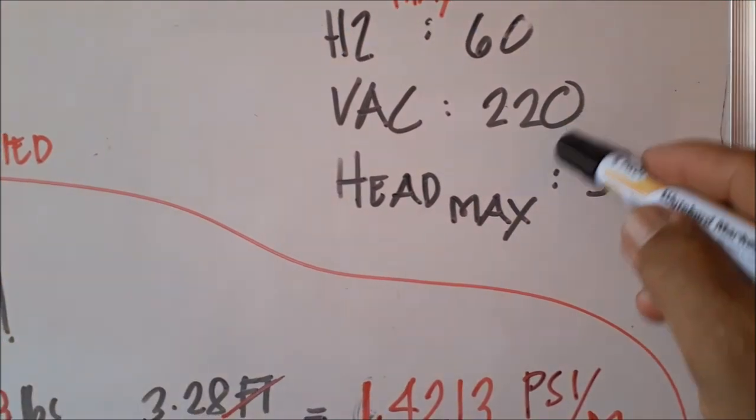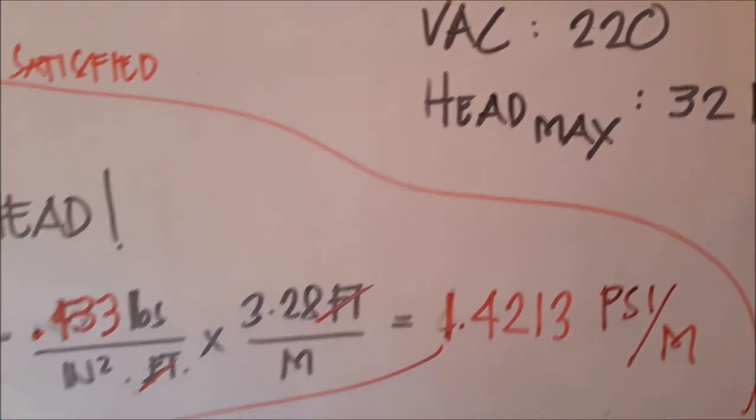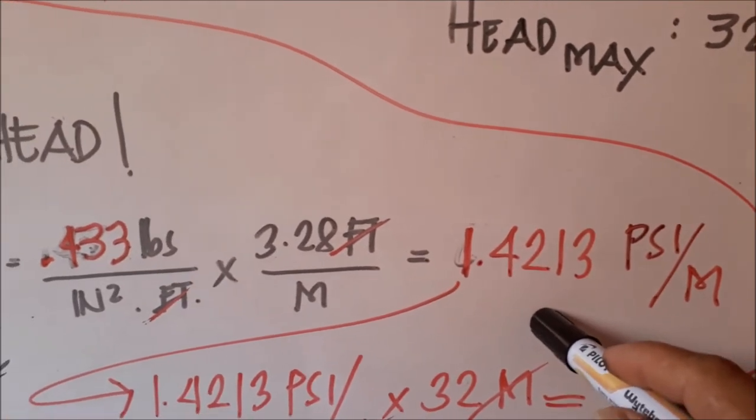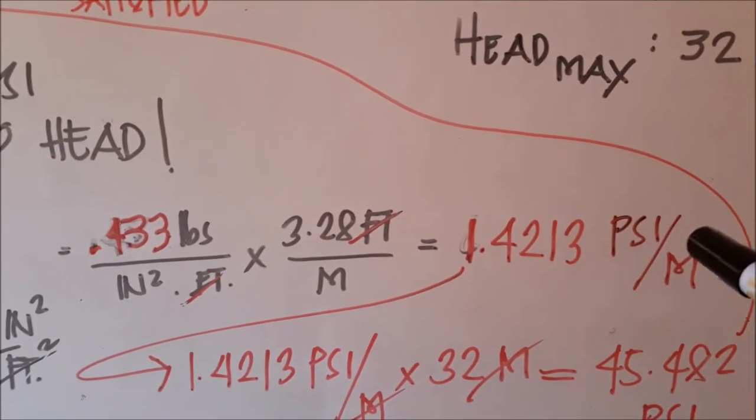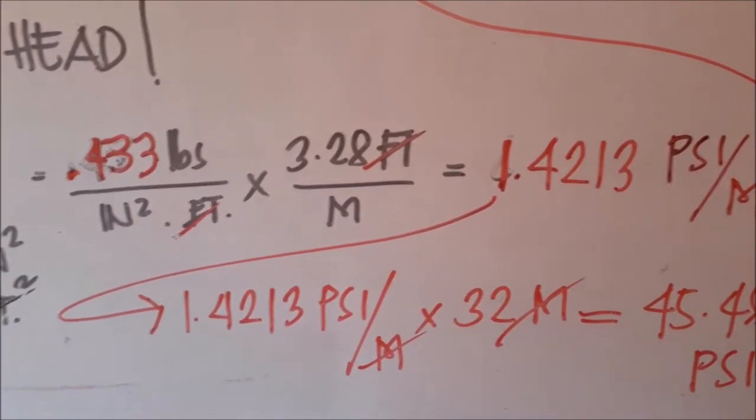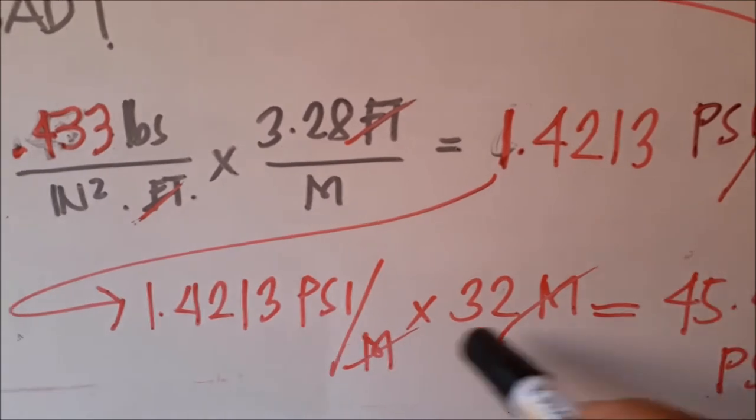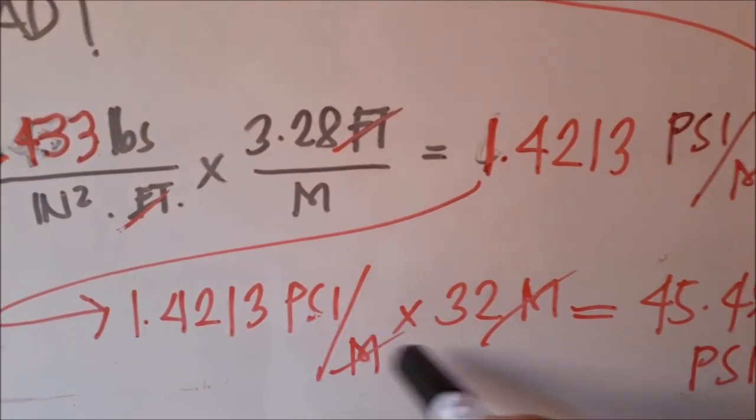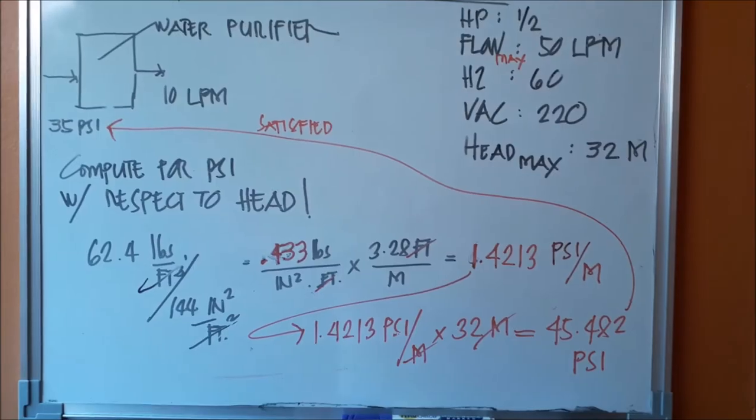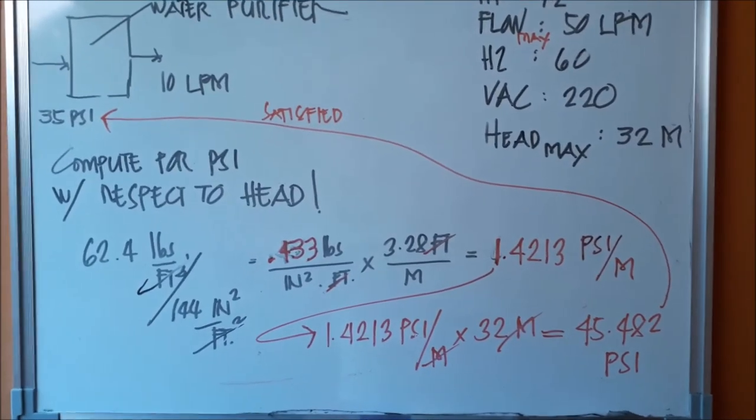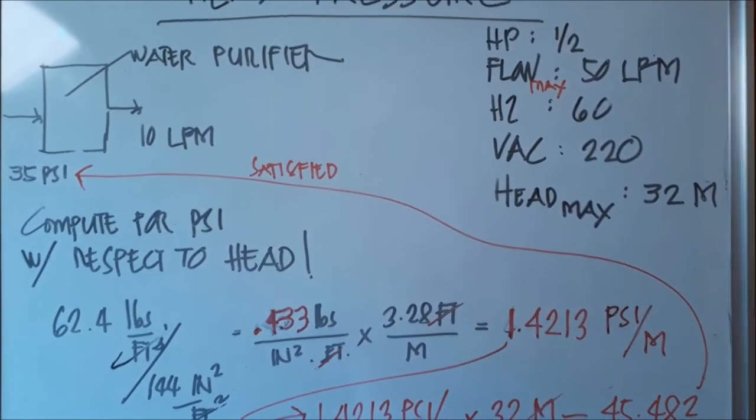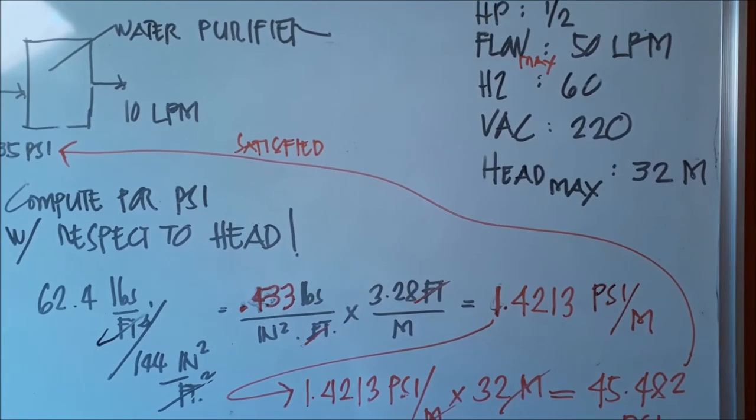Now let's find out the pressure at the base of the column if we have 32 meter head of water column. Let's use 1.4213 PSI per meter, multiply it by 32 meters. Cancel the meters, leaving PSI, equivalent to 45.482.